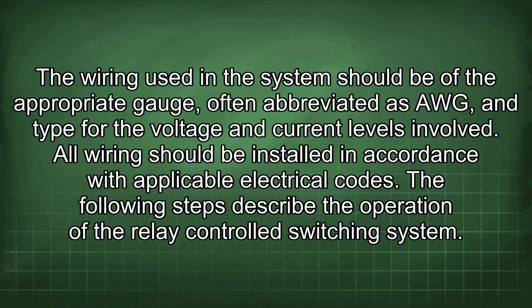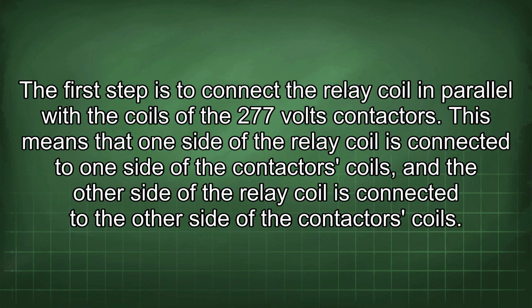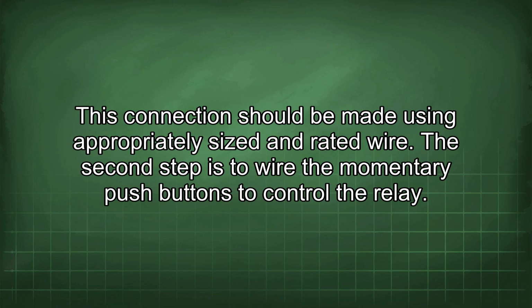The following steps describe the operation of the relay-controlled switching system. The first step is to connect the relay coil in parallel with the coils of the 277 volts contactors. This means that one side of the relay coil is connected to one side of the contactors coils, and the other side of the relay coil is connected to the other side of the contactors coils. This connection should be made using appropriately sized and rated wire. The second step is to wire the momentary push buttons to control the relay.